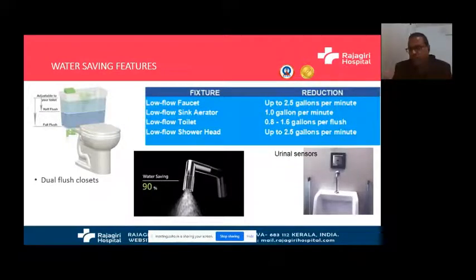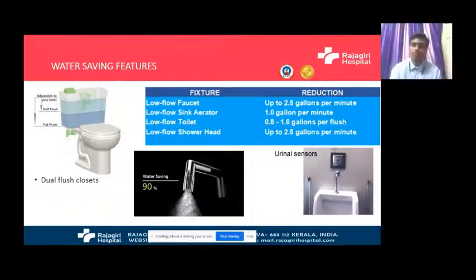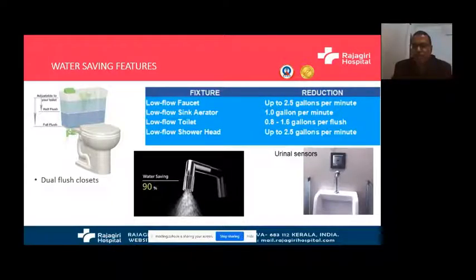Coming to water saving, we need almost 600 to 800 liters per patient per day in a hospital. So for a 1,000-bedded hospital, you can imagine the amount of water needed every day: 600 into 1,000, at least 6 lakh liters of water per day to run the hospital. It's a huge system, and you need a storage backup of at least 1 day. International standard says you need storage backup for 3 days in case there's a problem.